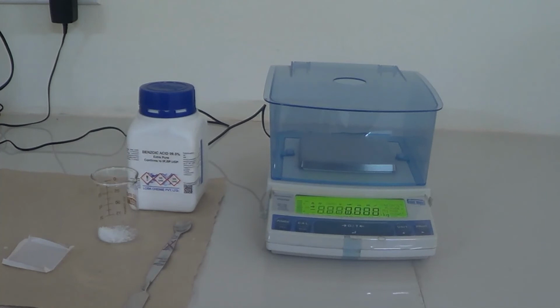Now, we'll see the precautions which we have to take whenever we weigh something. The balance should be placed at suitable location where vibration level or air current is very low. Always clean the debris or spilled material with camel's hair brush or equivalent. Whenever the balance is moved, it must be allowed to adjust to temperature of its new environment and then recalibrate it. This is all about the digital weighing balance. Thank you.